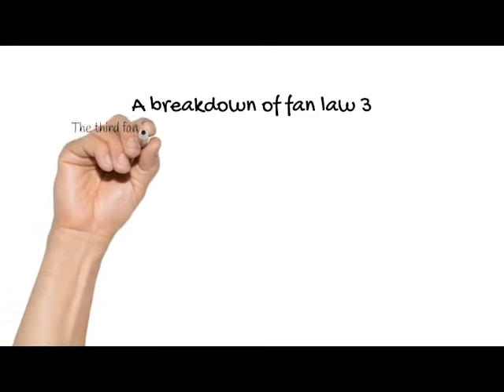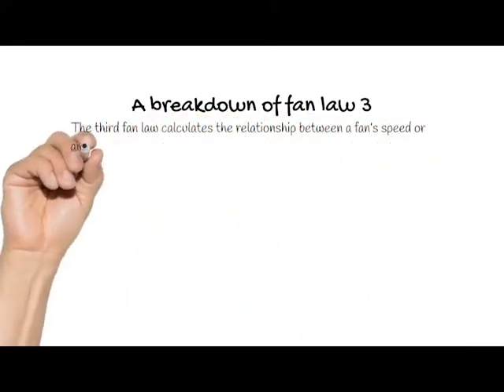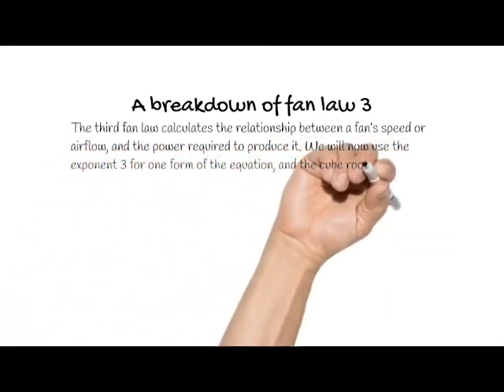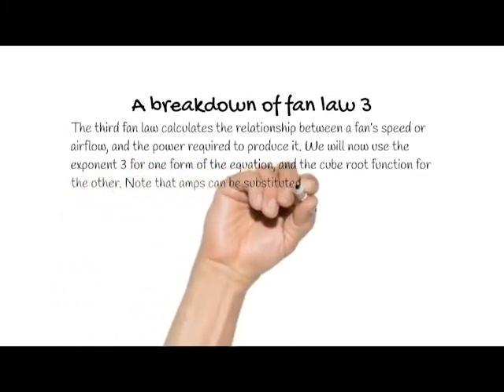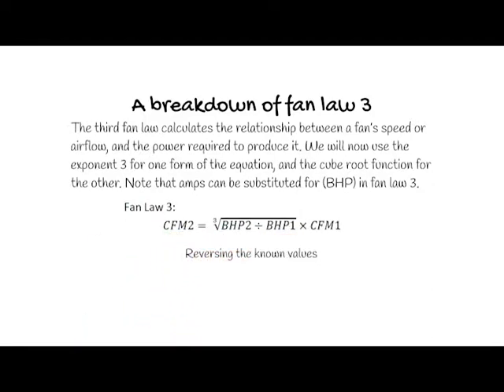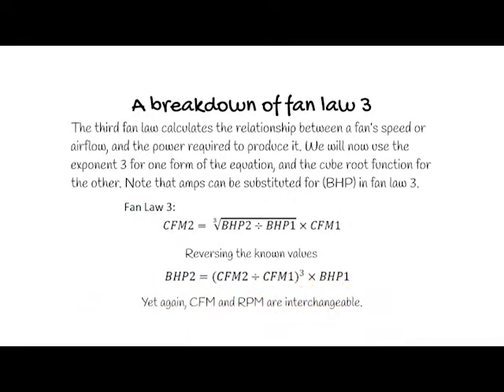On to fan law 3. The third fan law calculates the relationship between a fan's speed or airflow and the power required to produce it. We will now use the exponent 3 for one form of the equation and the cube root function for the other. Note that amps can be substituted for brake horsepower in fan law 3. Fan law 3 states CFM2 equals the cube root of (brake horsepower 2 divided by brake horsepower 1), multiplied by CFM1. If we reverse the known values, brake horsepower 2 equals (CFM2 divided by CFM1) cubed, multiplied by brake horsepower 1. CFM and RPM are interchangeable.